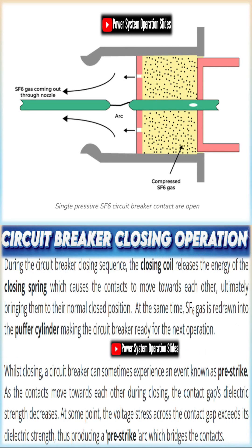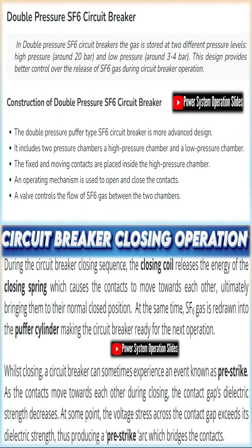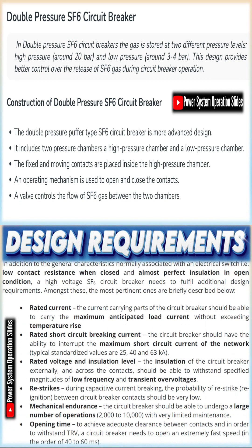To ensure reliability, SF6 breakers must meet specific design requirements, including high mechanical endurance, fast operating times, low contact resistance, complete gas-tight sealing, and conformance to international standards like IEC 62271.